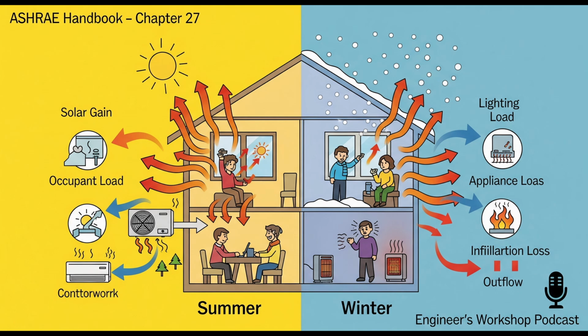Okay, beyond the big envelope loads, any other heat sources or losses the handbook mentions? Sure, appliances inside, obviously. They mention one kind of specific finding. Gas appliances under a typical kitchen hood might actually radiate a tiny bit more heat into the room than electric ones because of the hot combustion gases. Subtle difference. Yeah. And motors, like in fans or appliances, they generate heat. Whether that adds to your cooling needs depends if the motor's inside the conditioned space or, say, out in the garage. Makes sense. And then ductwork. Yeah. That sounds important. Hugely important. Ducts running through unconditioned areas like attics or crawl spaces can lose heated air in winter or gain heat in summer before the air even gets to the room.